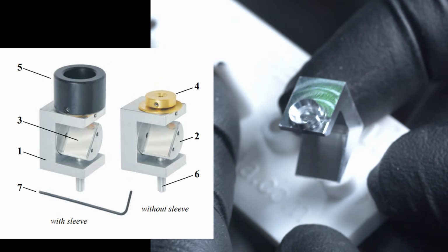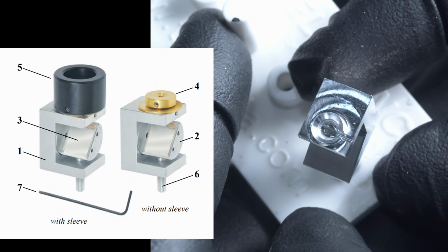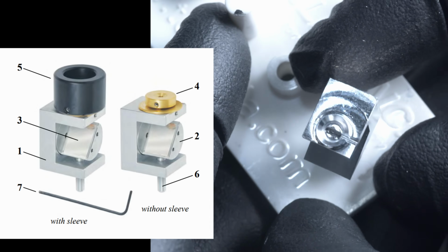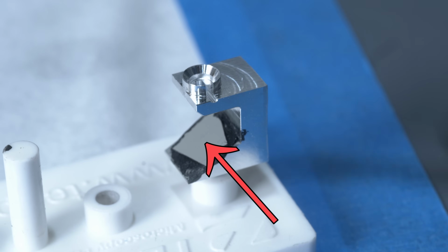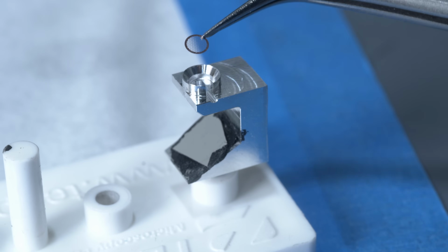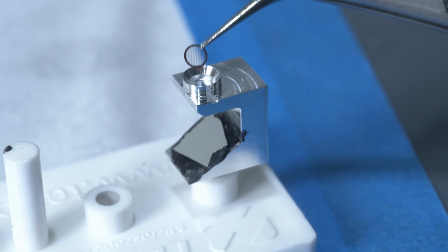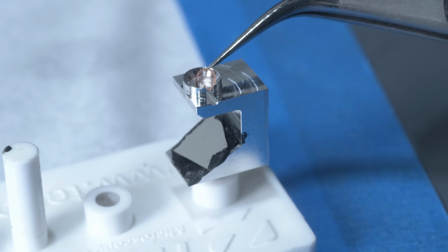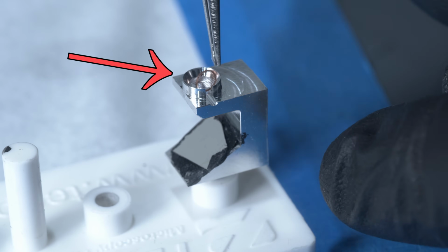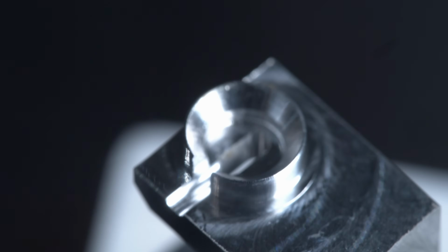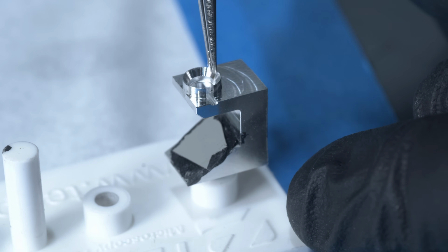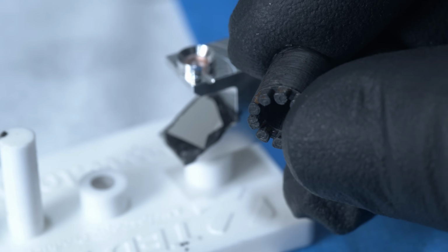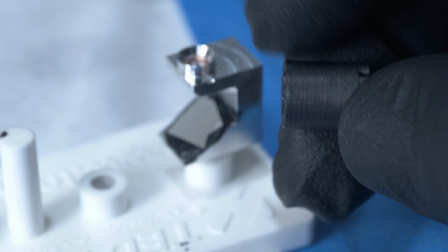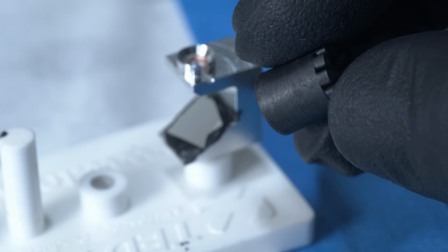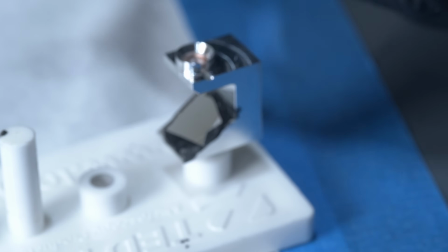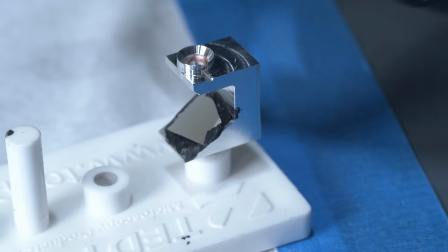You can see my model is effectively the same as the Pelco variety, just a little simplified. I coated a cover slip with 100 nanometers of silver, and I'm using that as the angled secondary conversion plate at the bottom. There's a small cup to hold the sample grid, a small aperture to let electrons through, and then I 3D printed this sleeve to go on top, and the sleeve is coated in just some graphite to make it conductive. And the idea here is it just needs to absorb any secondary electrons coming out of the top of the sample and then conduct them to ground.